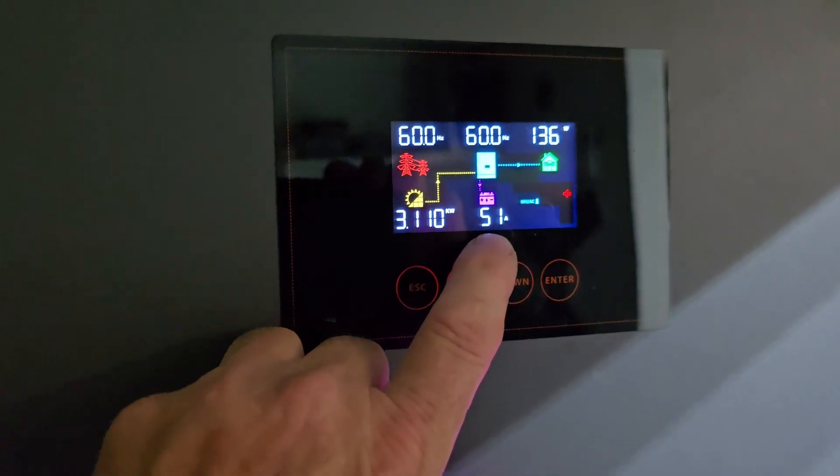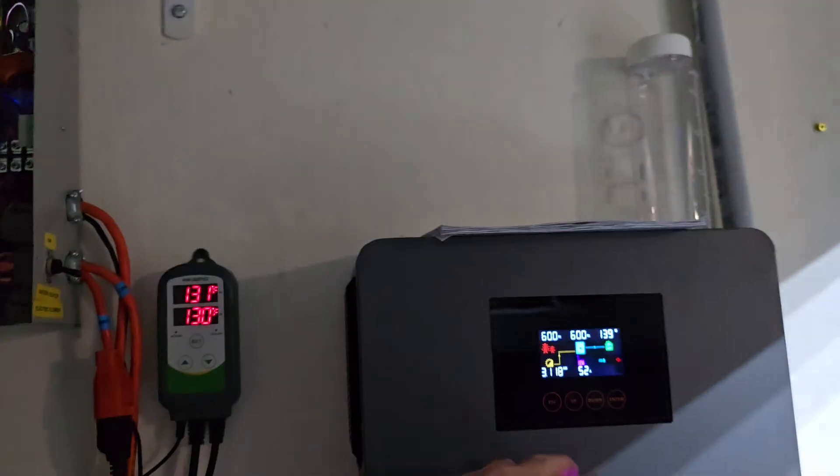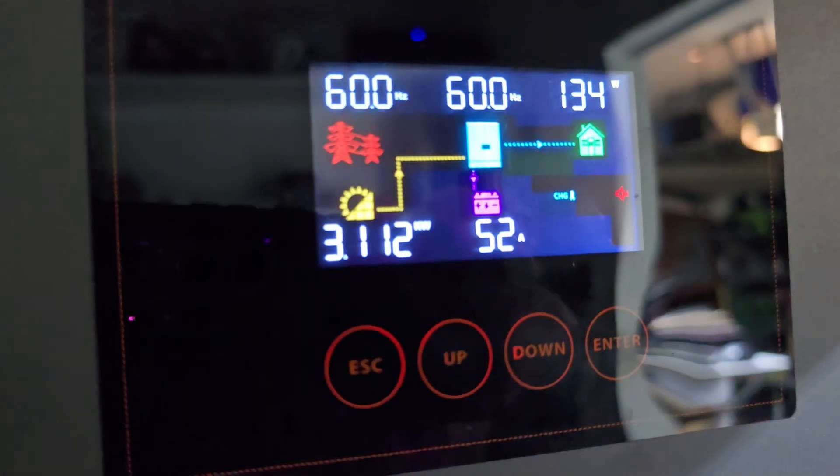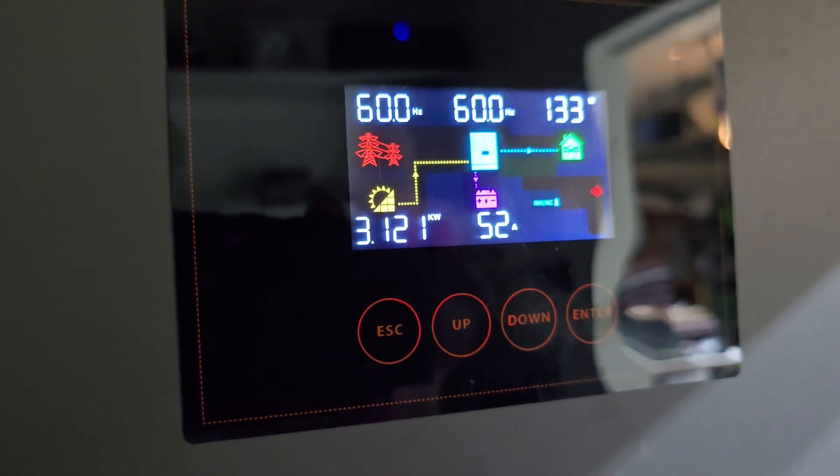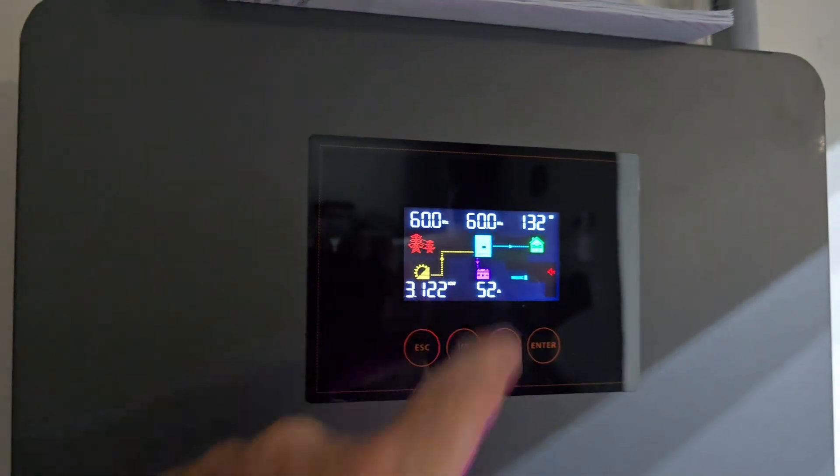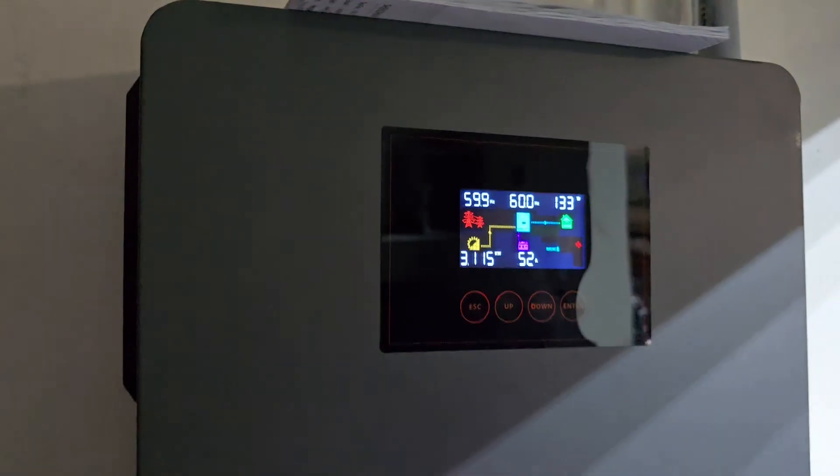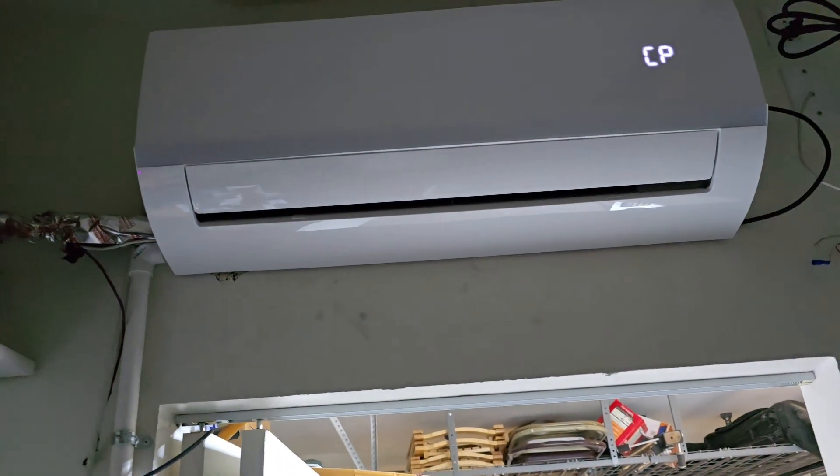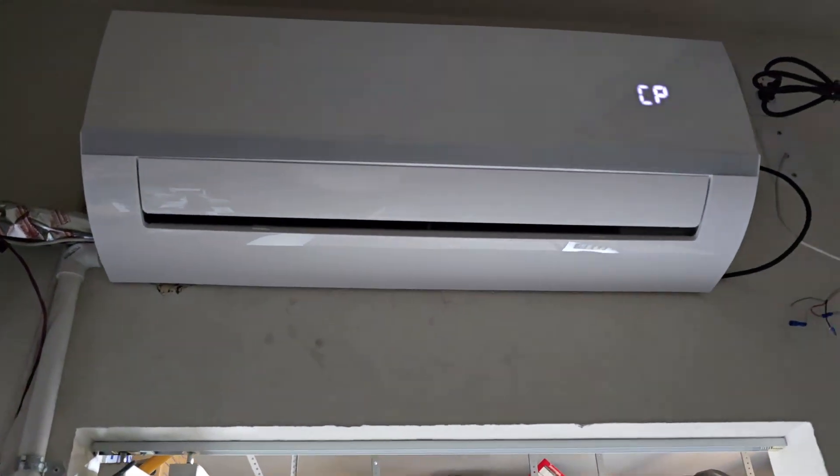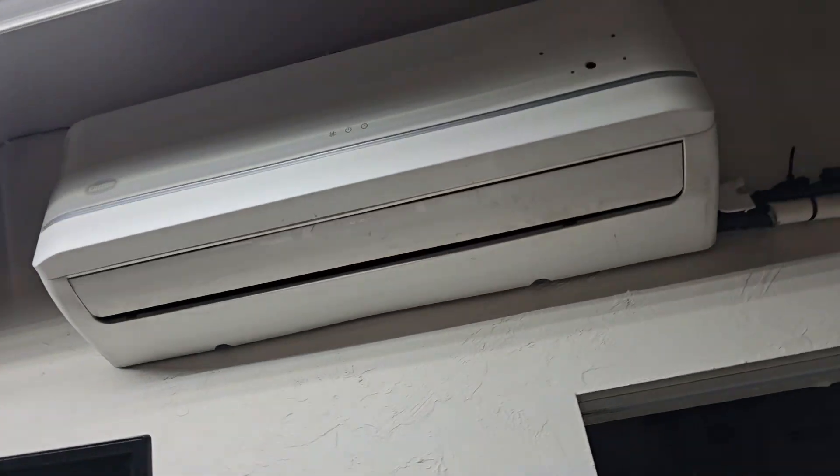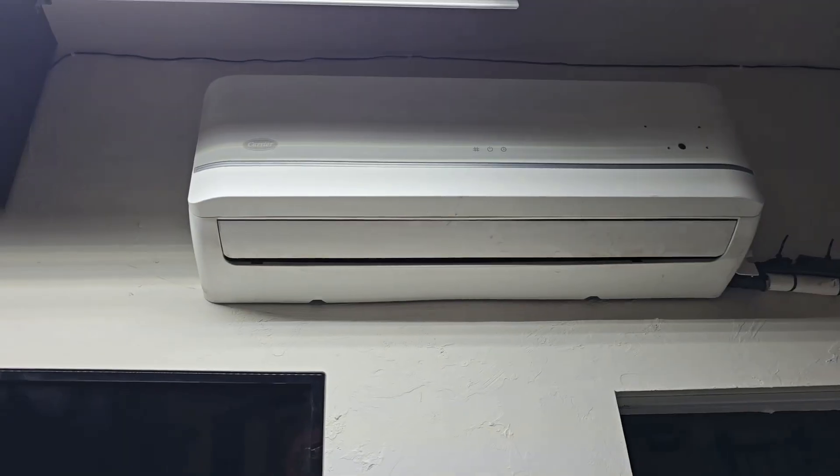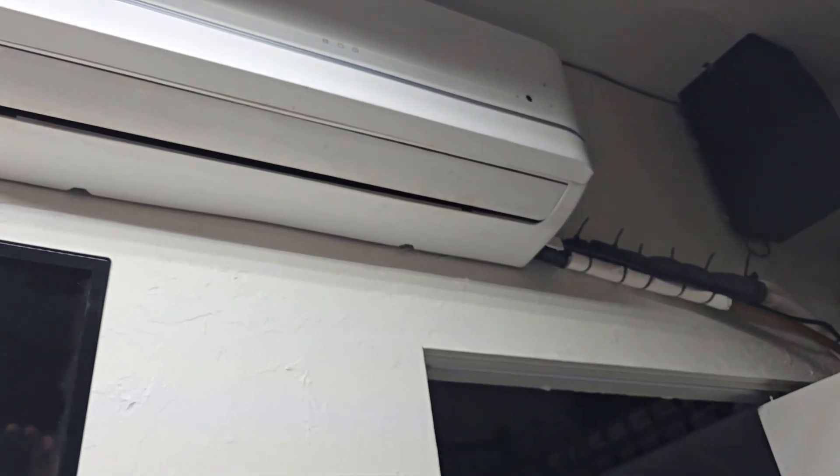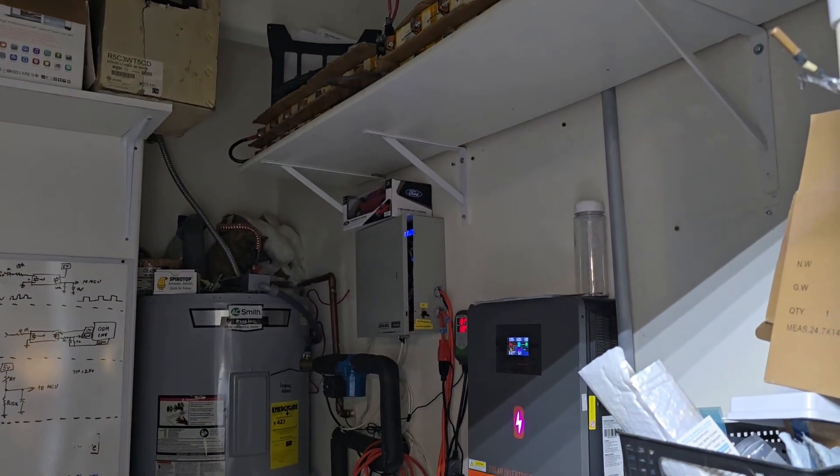Now this sucker's going to be putting more power, over 50 amps at 48 volts going into my batteries, over 50 amps on the wire, which is this big fat wire back there. It's as thick as my pinky, into those batteries. 3.1 kilowatts right now going into my 48 volt array. Fully charged at 56 volts, so it's 52 volts now. It'll be fully charged here in a little bit at that rate. Pretty kick ass. The kick ass thing about all this stuff is if my power goes off, this still runs. Once I get some more ductless stuff hooked up, I'll be able to run a zone when my power goes off, which it sometimes does for up to three, four hours in the middle of the night in Glendale in monsoon season. We have above ground power wires here, so they like to take a shit. Anyway, I think that'll do it for that. I'll just maybe do an update another time after I let it run a while.